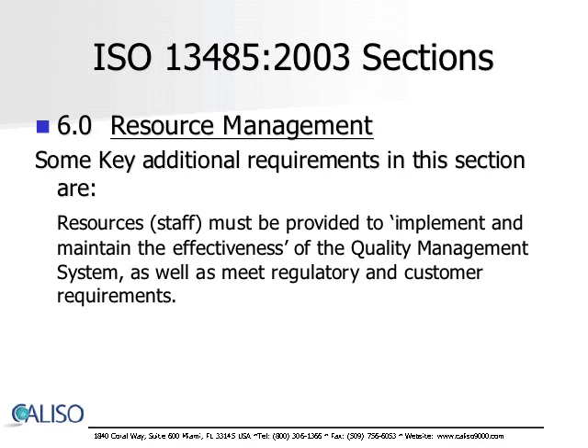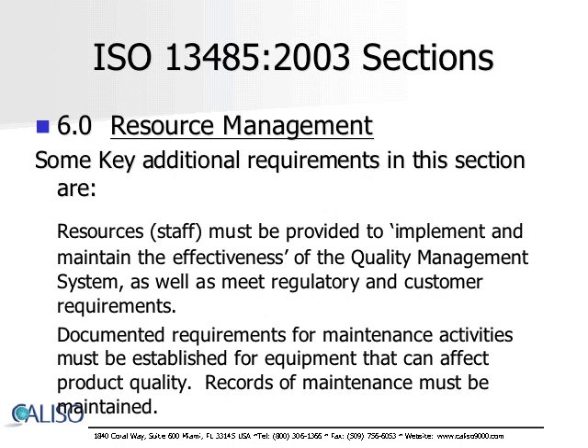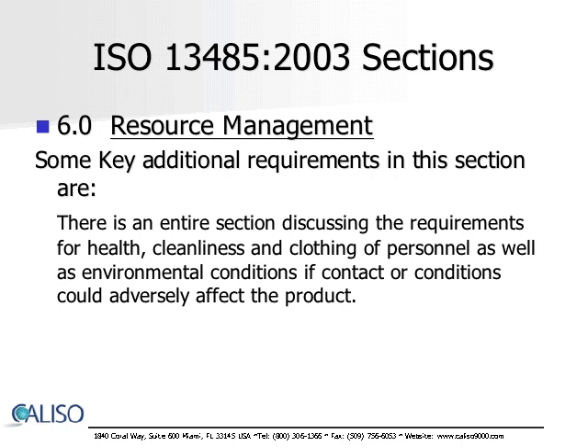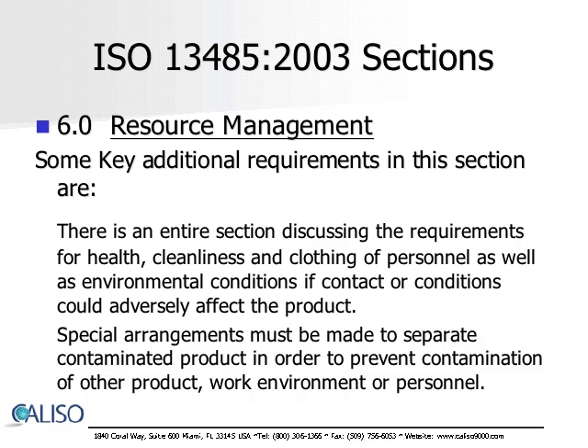Some key additional requirements found in this section: resources or staff must be provided to implement and maintain the effectiveness of the quality management system as well as meet regulatory and customer requirements. Documented requirements for maintenance activities must be established for equipment that can affect product quality, and records of maintenance must be maintained. There is an entire section discussing requirements for health, cleanliness, and clothing of personnel as well as environmental conditions if contact or conditions could adversely affect the product. Also, special arrangements must be made to separate contaminated product in order to prevent contamination of other product, work environment, or personnel.